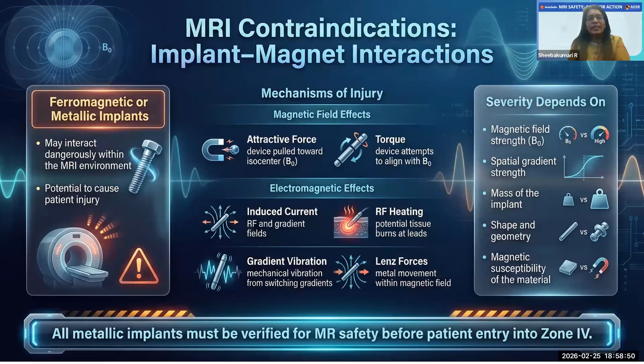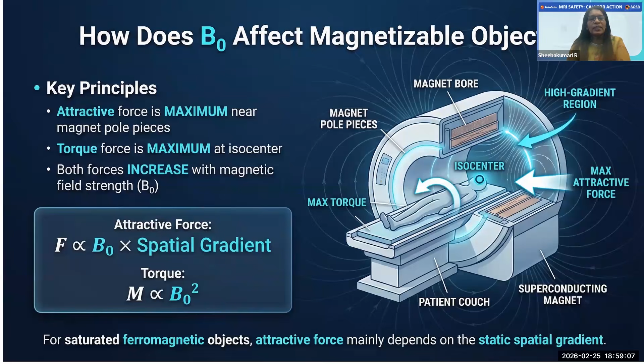The severity of all these interactions depends upon the field strength, the spatial gradient of the magnet, the mass of the implant, shape and geometry, and the magnetic susceptibility of the material. An implant has its maximum attractive force near the pole pieces, where the static magnetic field gradient is higher. The force of attraction is directly proportional to B0 times the spatial gradient, whereas the torque force will be highest at the center. Usually ferromagnetic implants, that is implants made of cobalt, nickel, martensitic steel, mu metal, or pure iron, can have strong attractive and torque forces in an MR environment.